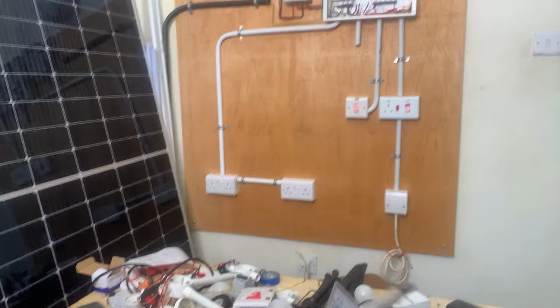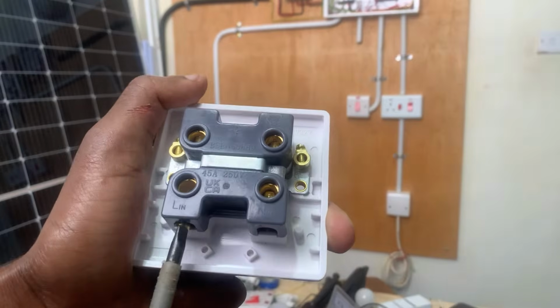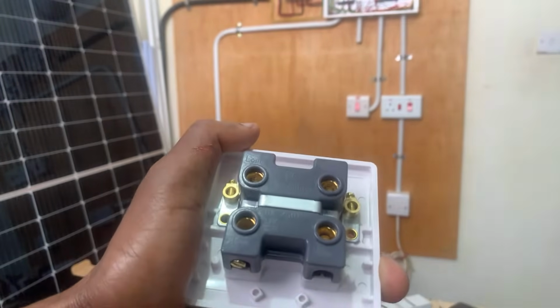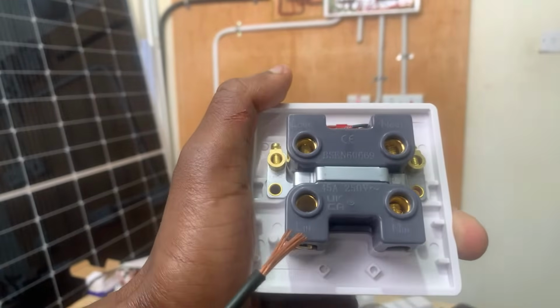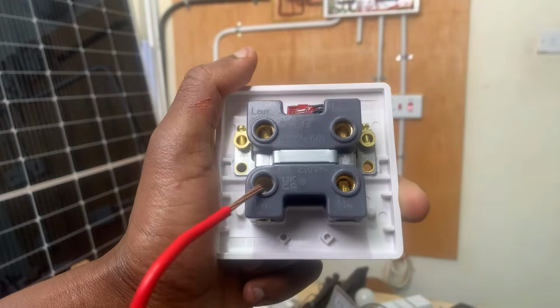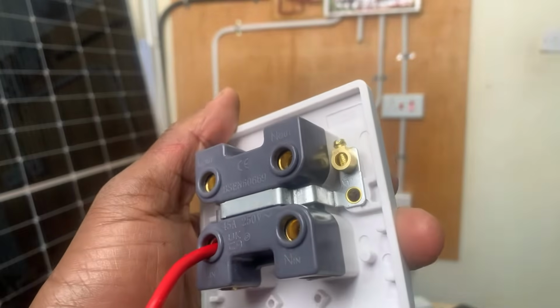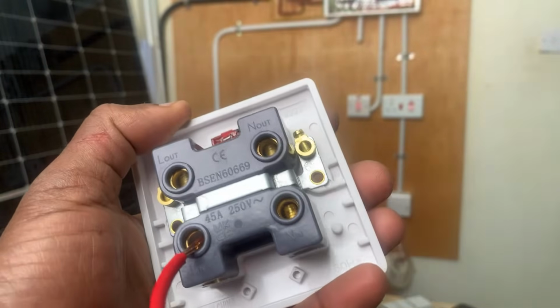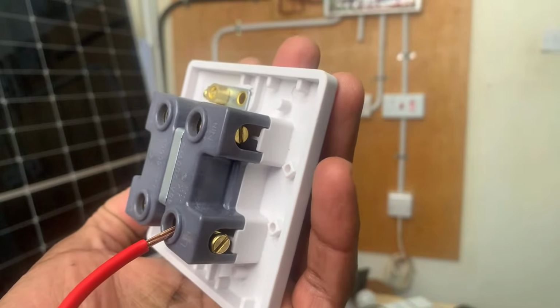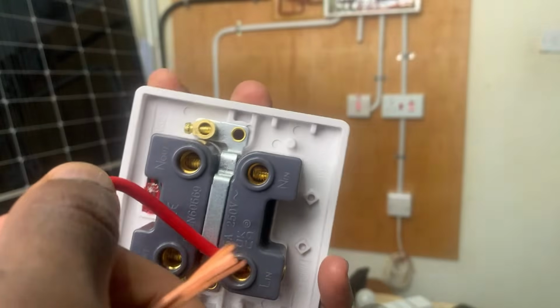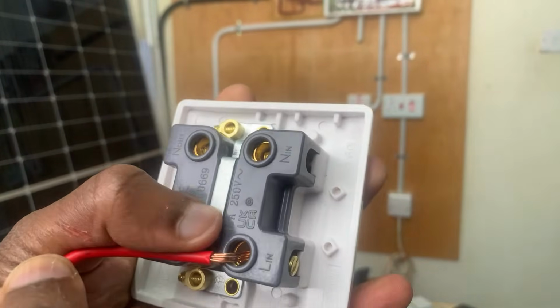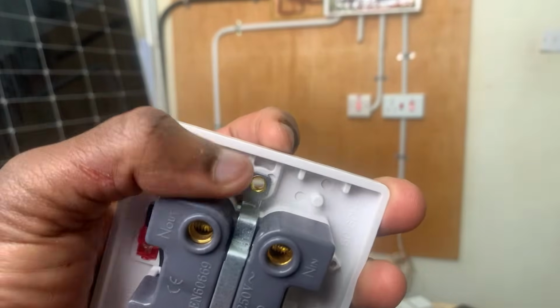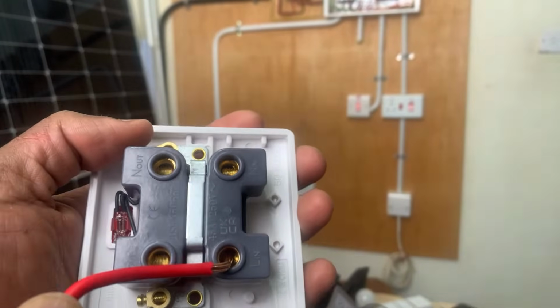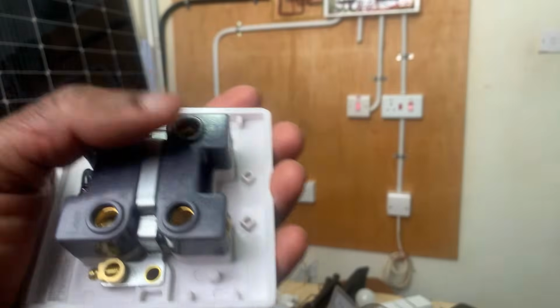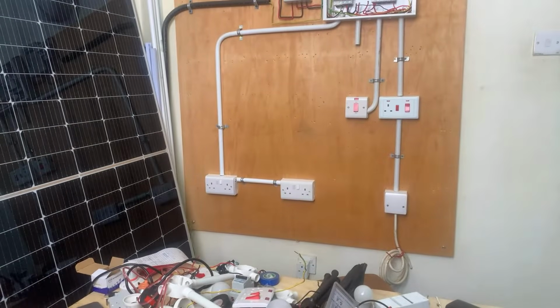If you don't tighten this screw, there is a problem with your work because it gives much allowance. Again, with this cable, this one is L in, so we use the red because it's the phase. If you just insert the cable, it will go all in. But if someone screws and leaves parts of the cable exposed here, it's risky—if by accident it touches the earth connection, and we know the metallic part goes all the way to the earth connection, it will short circuit, leading to the circuit breaker tripping, and that circuit will not have power supply because it has tripped.